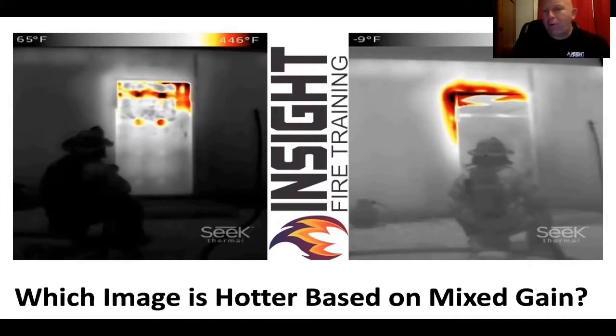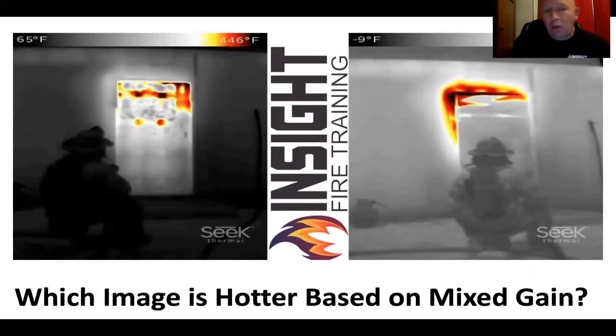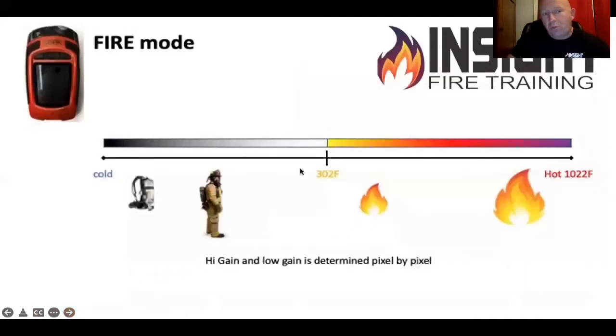But what do you notice about the picture on the left? What has changed? What is harder to see now? The firefighter is harder to see, and what can you not see that's beside the firefighter also? The propane tank is harder to see. This is how you know the camera is seeing more heat — when it focuses in on the heat source, the outside edges start to get darker. Just like when your pupil switches from dilated to constricted. This is how the camera performs in mixed gain mode.